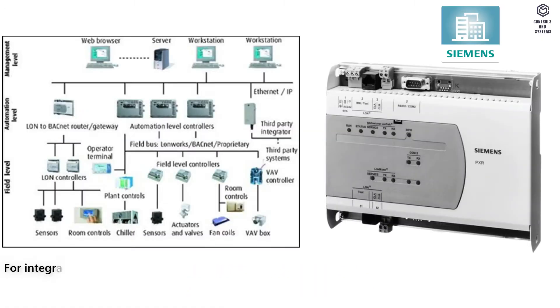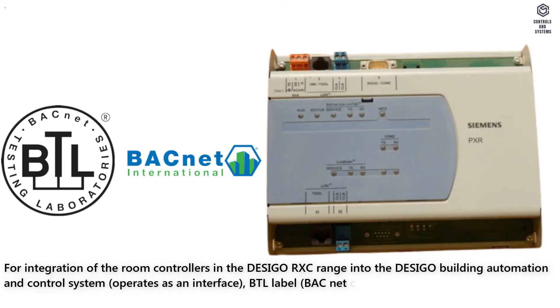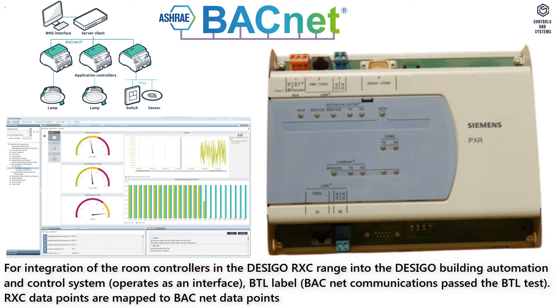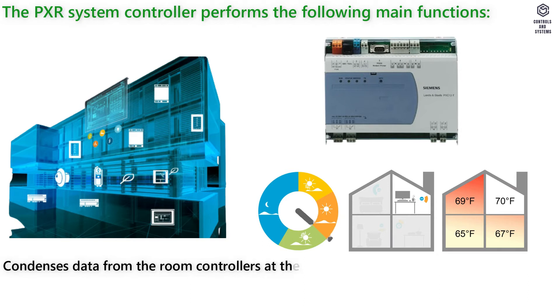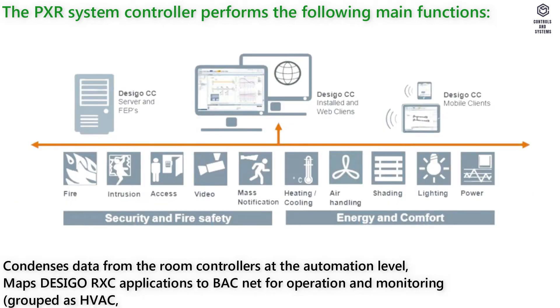Overview. The PXR operates as an interface for integration of the room controllers and the Desigo RxC range into the Desigo building automation and control system. BACnet communications pass the BTL test. RxC data points are mapped to BACnet data points and vice versa. The PXR system controller condenses data from room controllers, mapping Desigo RxC applications to BACnet for operation and monitoring, grouped as HVAC, lighting, and blind control functions.